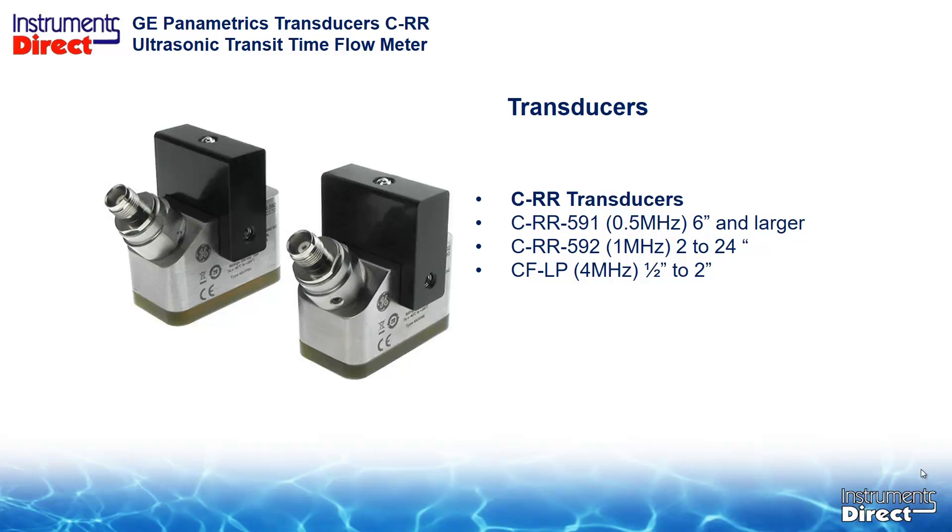The CRR-592 is a 1MHz clamp-on transducer for pipe sizes 2 to 24 inches. And the CRR-591 is a 0.5MHz transducer for pipe sizes 6 inches and larger.